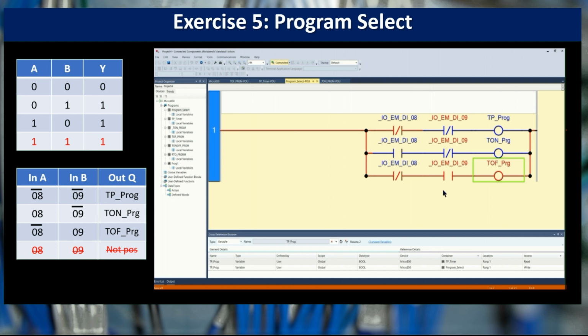The other problem is that without interlocking, there's the difference between a switch that has failed and a switch that is left in the open position. Well, the wire's off, it's like open, so you may not get the signal that you want. Conversely, if a contact welds shut, then it's always on. And when changing the state, with the interlocks, you're giving yourself two conditions to rely on to change the outcome of the rung of logic.